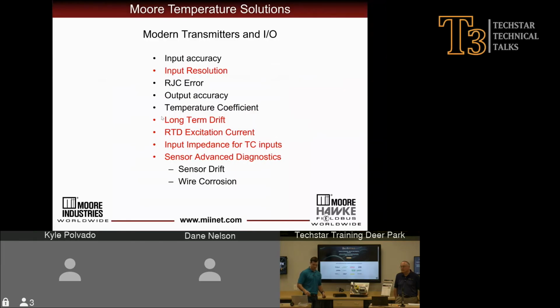So looking at modern transmitters and I/O, most temperature transmitters on the market have very similar specifications these days. But some things that perhaps you should look into for high accuracy temperature measurements are maybe input resolution. Input resolution is something that you want the highest available. 20-bit resolution is what we have on Moore Industries temperature transmitters. And that's an industry best practice standard. So the input resolution is going to allow you to see more defined step changes in your temperature process.